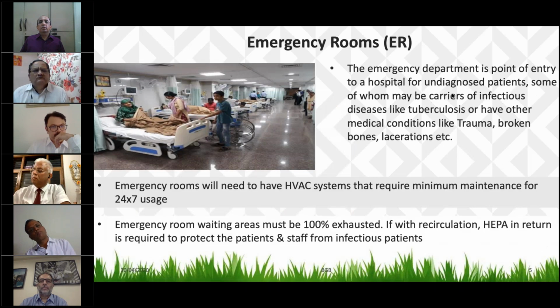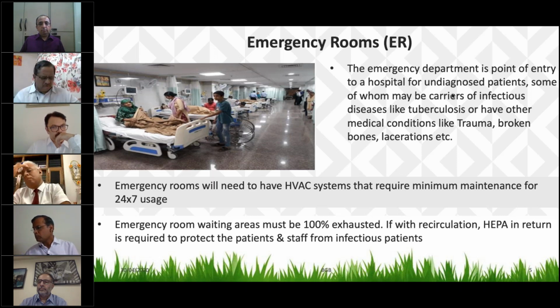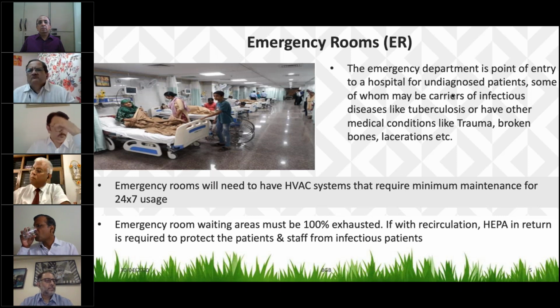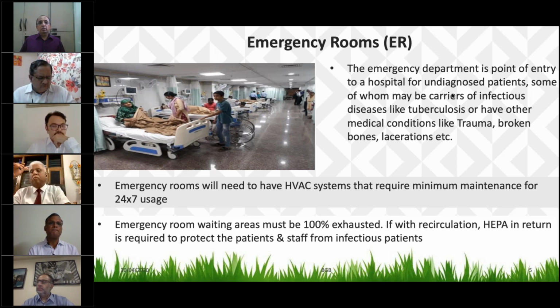No, I think this is as far as the particular rooms that you mentioned. Apart from this, you mentioned OPD and IPD. Basically, many of these rooms are served by, what Vishal mentioned, high walls or cassettes and all that. We have to ensure that the level of pathogens in these particular areas is kept down by having a certain amount of fresh air coming in, either by an improvised method in this context or a permanent method in the future. So you have to have fresh air and you have to have an exhaust in these areas to make them safe. I think that covers the various types of rooms that you mentioned, Mihir.